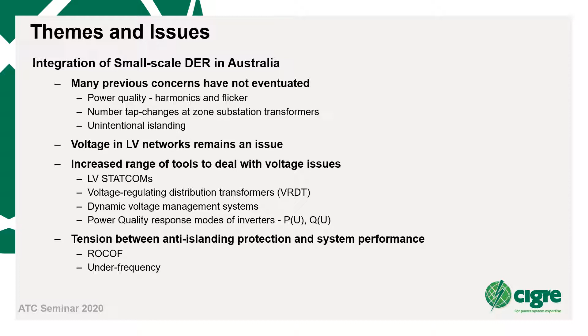From an anti-islanding perspective, the desire is to have tight settings for both these protections to enable fast tripping. However, from a system controls perspective, it is preferable to have looser settings so that DER can stay connected and continue to generate during a system disturbance.